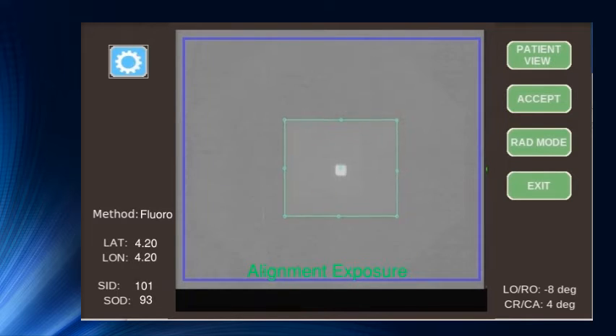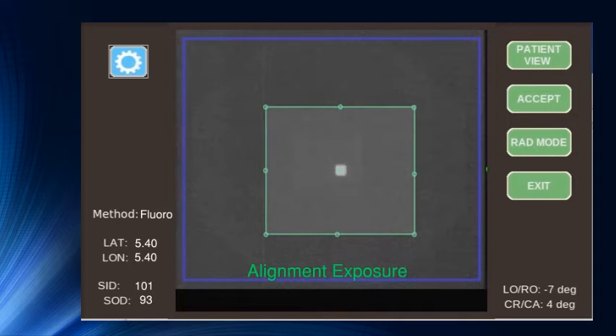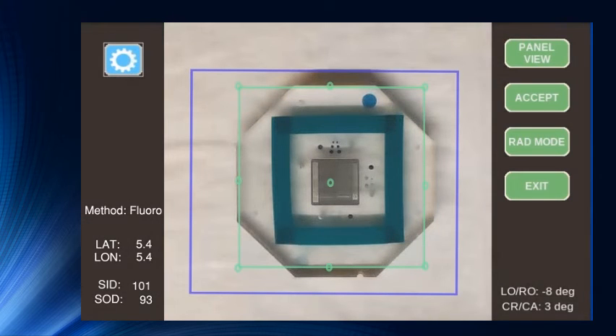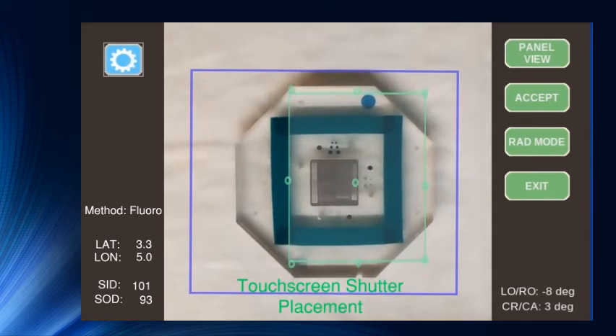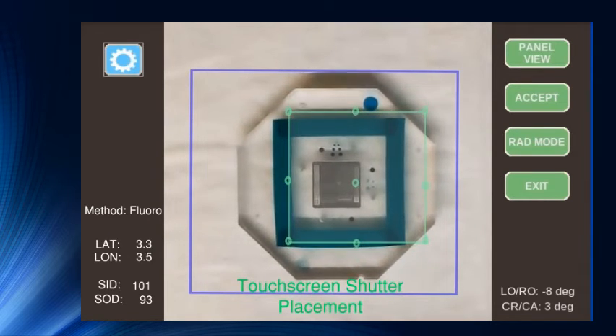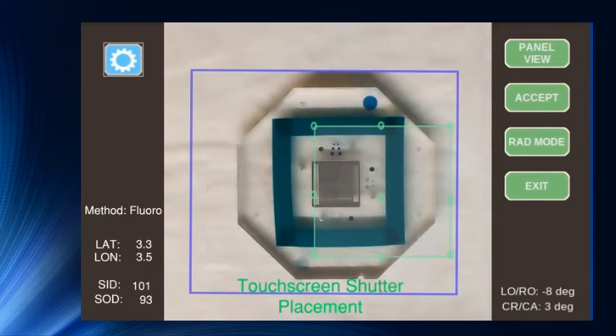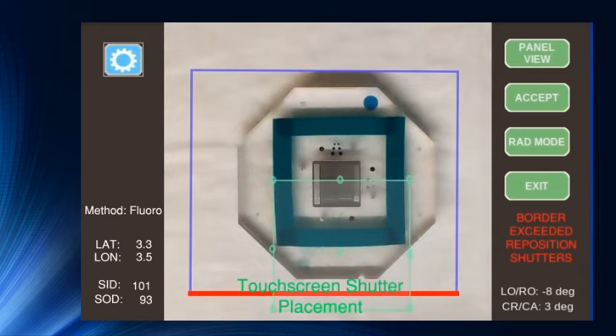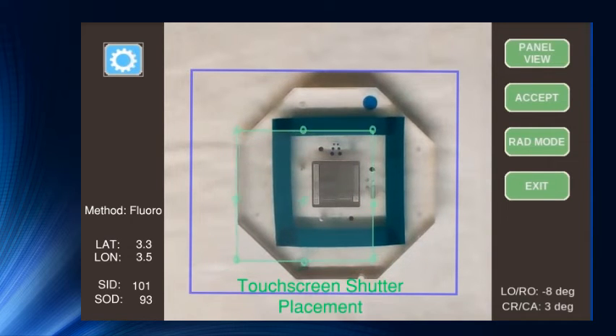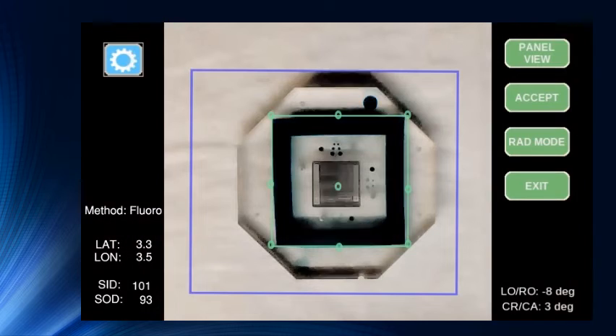The workstation computer transmits the alignment image to the MVC. The MVC then calculates the present location of the X-ray source with respect to the detector. The MVC will automatically reposition the shutters to align the radiation beam to the detector, and the size of the collimated area is adjusted for the anatomic region being imaged. At this point, manual manipulations of the beam size and location can be performed using the pinch and swipe touch panel actions. Pinching the touch panel, as you would to zoom in or out on a smartphone, will define the shutter opening relative to the beam output size. While swiping will move the shutter openings, adjusting the location of the beam itself while maintaining the desired shutter opening.